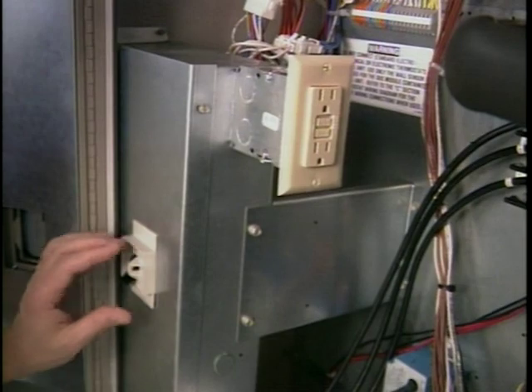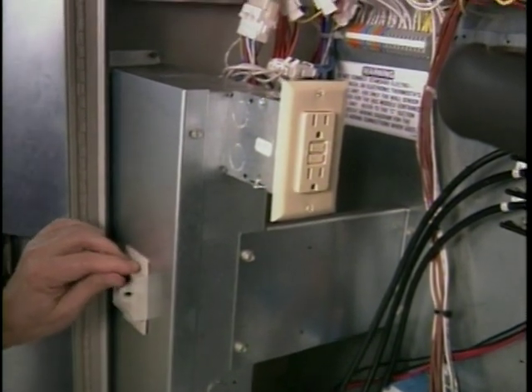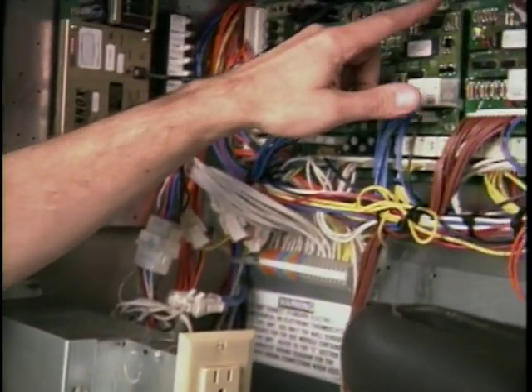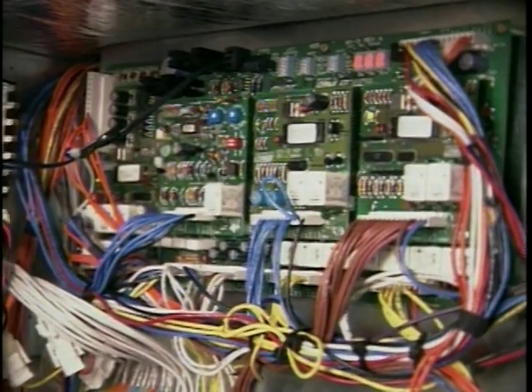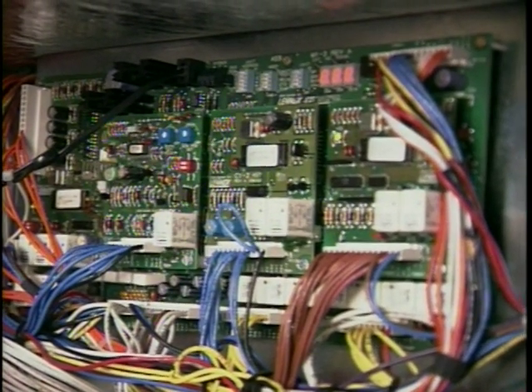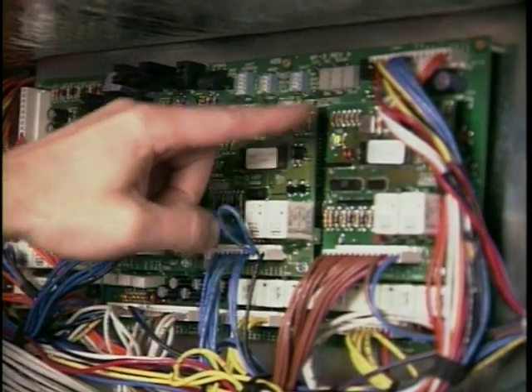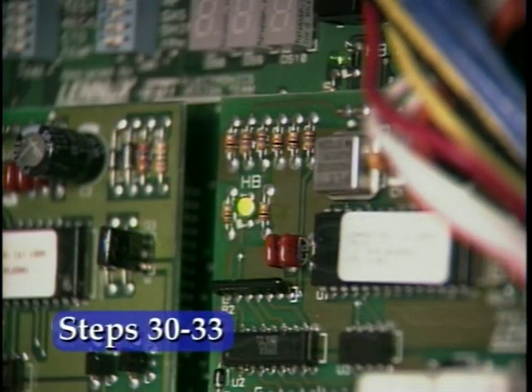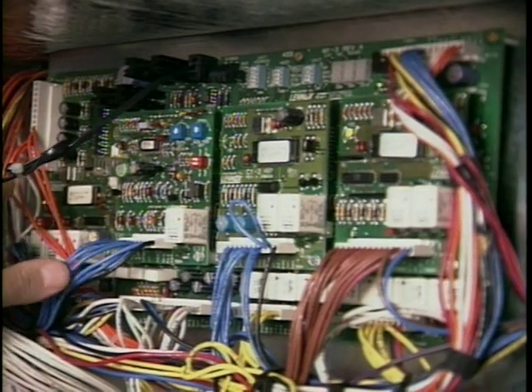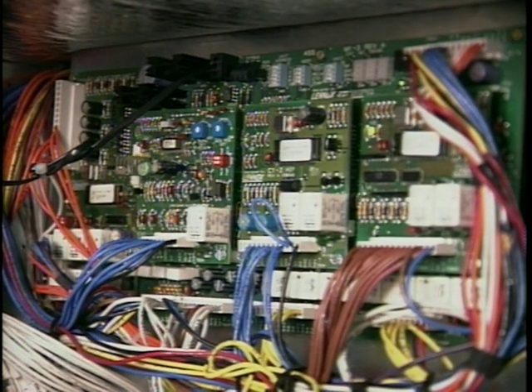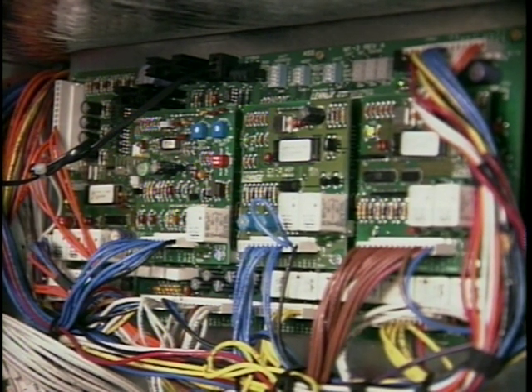After these checks are complete, turn on the electrical disconnect. The LED readout on the IMC will go through a self-test, flashing 888 on the display, and then go blank. This is the normal operation. Check that the heartbeat LED on each board is flashing steadily. If you don't have a normal flashing indication, contact Lennox National Accounts before proceeding.